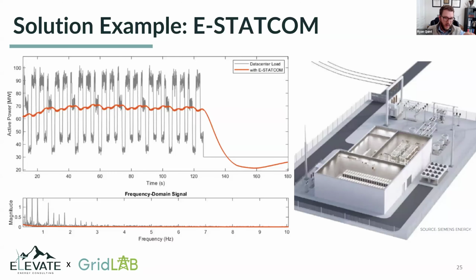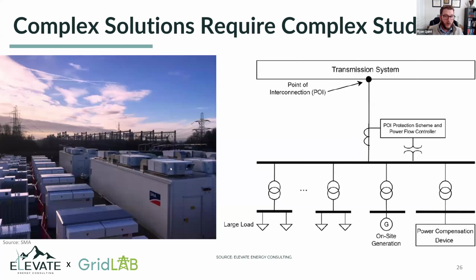That gray line, for example, some information Siemens provided, shows a rather jittery data center load, and we can smooth that out quite a bit with an e-StatCom. How much we smooth and how fast it can perform depends on how it's designed, tuned, and sized. This can be really useful to eliminate some subsynchronous oscillations, stability concerns, and ramping issues.